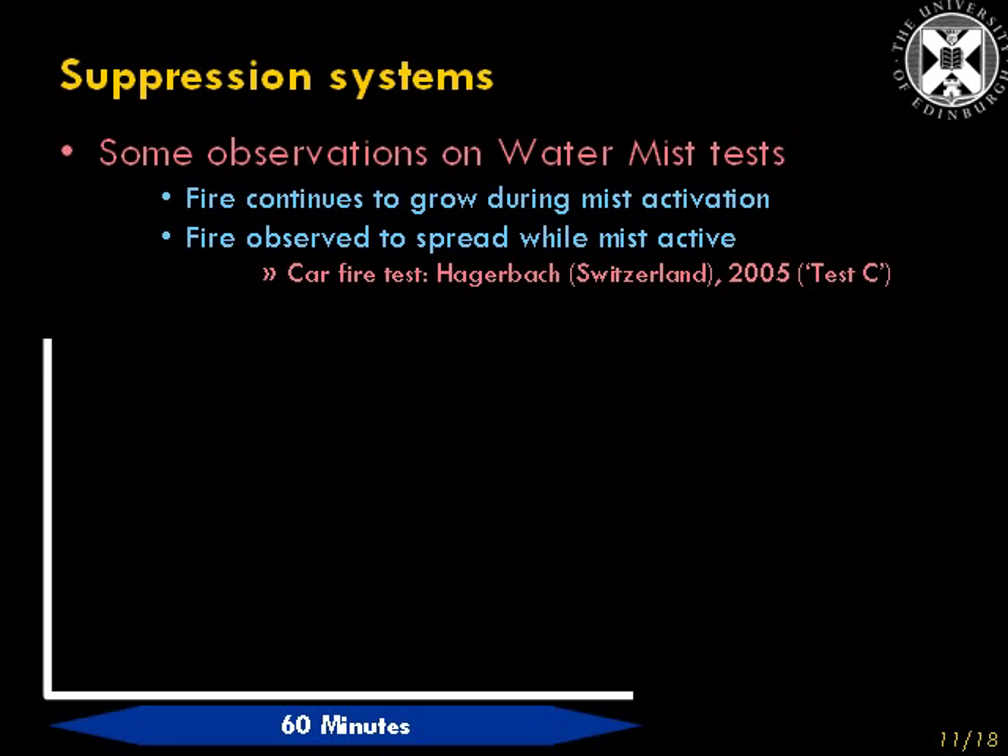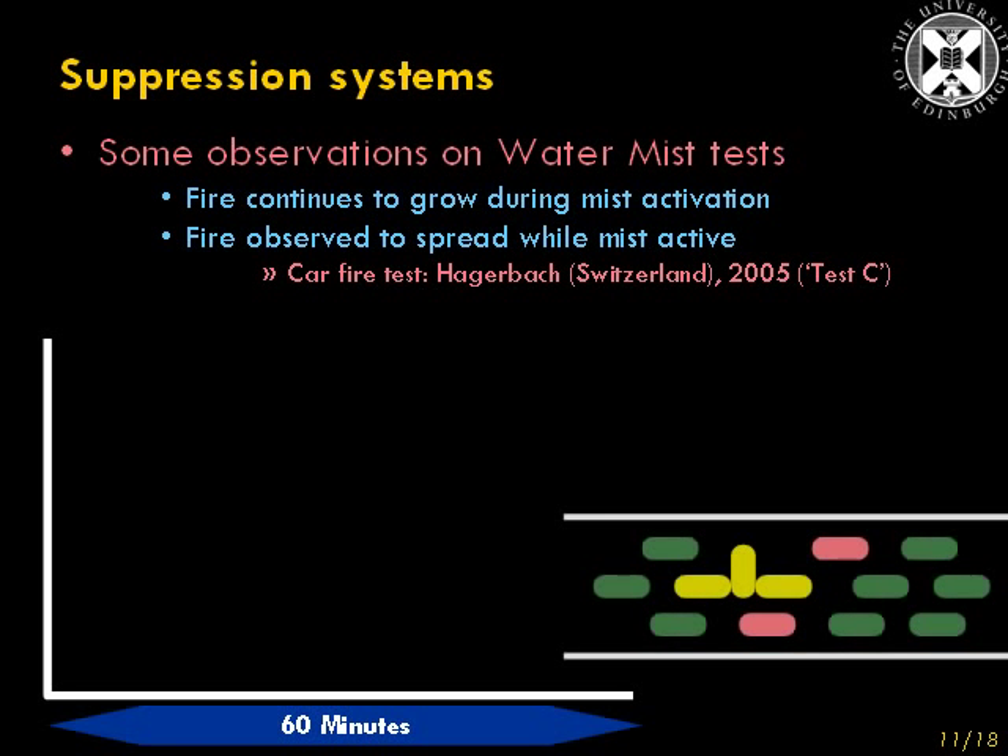Some observations from a different test. This one was carried out in Hagerbach in Switzerland in 2005 and involved an arrangement of cars. The three cars indicated in yellow in that diagram were the ones initially set on fire, and the other blue, green, and pink cars around them were to see if the fire would spread to those vehicles or not.